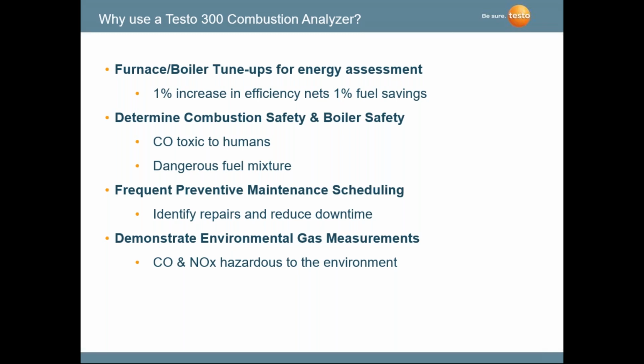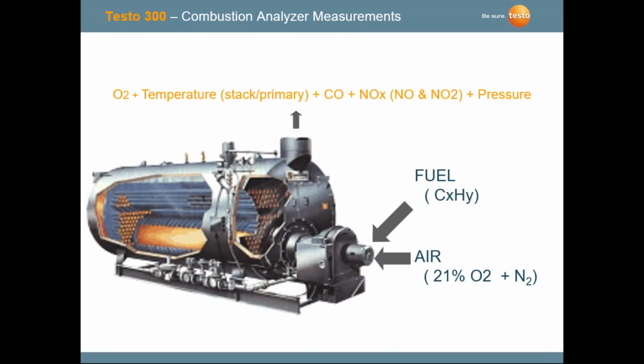Also, obviously, it's combustion efficiency. It's all about fuel savings, especially when you get into commercial and industrial boilers, where the fuel costs are much higher than maybe a residential furnace, so combustion efficiency is important. And then the last thing is environmental: measuring for clean air, looking at NOx and SO2 measurements.